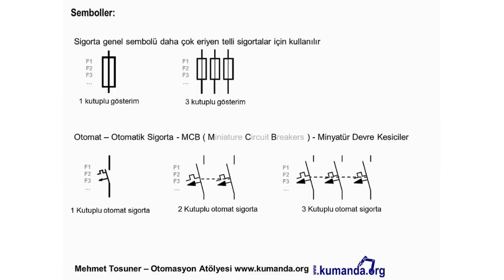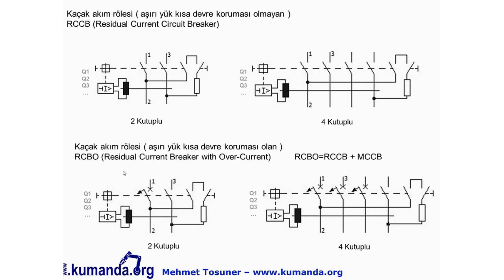Sembollere göz atalım: genel sigorta sembolü eriyen telli sigortalar için kullanılır. MCB için 1, 2 ve 3 kutuplu semboller var; ok manyetik açıcıyı (kısa devrelerde), kare ise termik açıcıyı (aşırı yüklerde) gösterir. RCCB sembolünde toroid sistemi sembolize edilir, termik-manyetik koruma yoktur. RCBO sembolünde çarpı yük ayırcısını, ok ise kısa devre korumasını gösterir. IEC standartlarındaki sembollerle ilgili ayrı bir video hazırlamayı düşünüyorum.